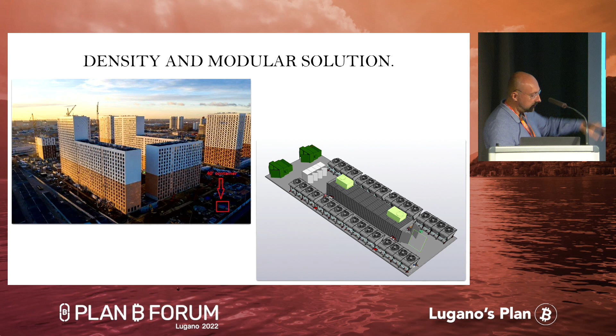From the right picture, you can see actual information from one of the running containers. This is a specially designed miner, but just half of it. We can see 3.77 total power in megawatts, and the cooling system fans at only 50%. It was 45 degrees ambient temperature outside, meaning we can put double the amount of miners. This was the first revision of the miners - we have several newer revisions with double capacity, confirming we can cool at least 8 megawatts with that cooling system at 45 degrees ambient temperature.